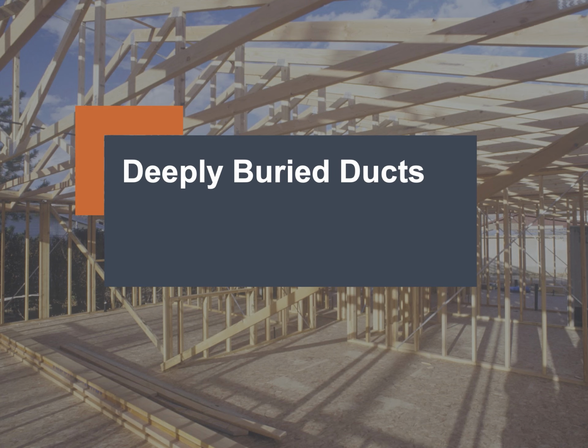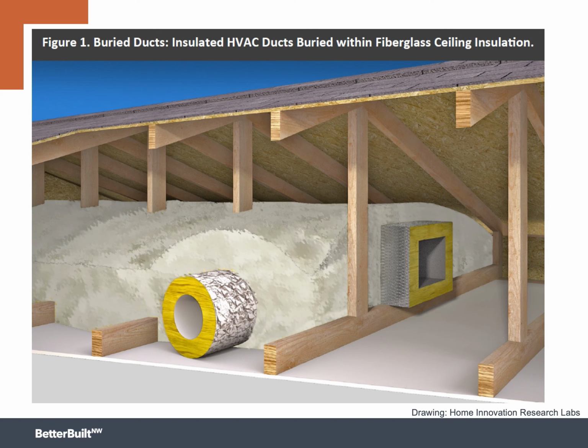Let's have a look at the Oregon Residential Specialty Code, or ORSC, requirements for deeply buried ducts. This aligns with the Washington State Energy Code Table 406.3 credit for deeply buried ducts as well. Essentially, the ductwork is installed so that it touches the attic floor. When it's not possible to contact the ceiling drywall directly, it can be as close as possible.